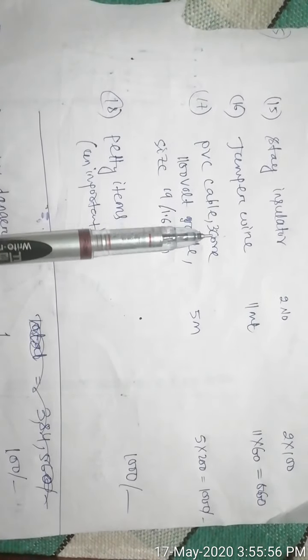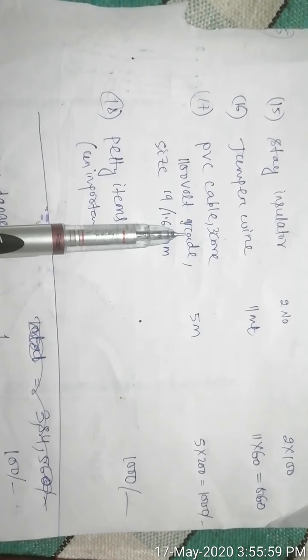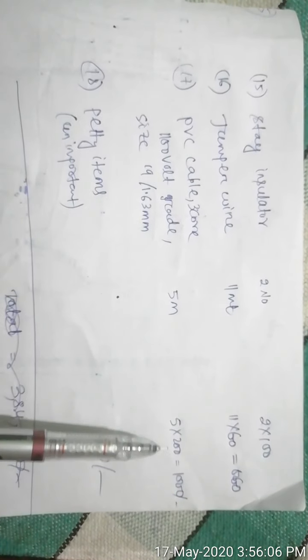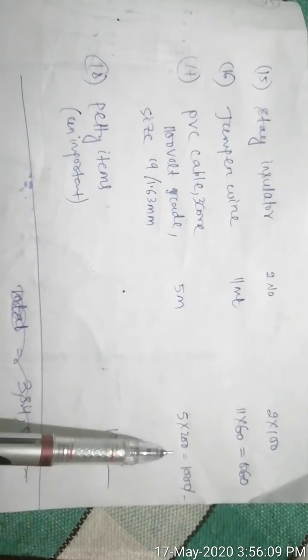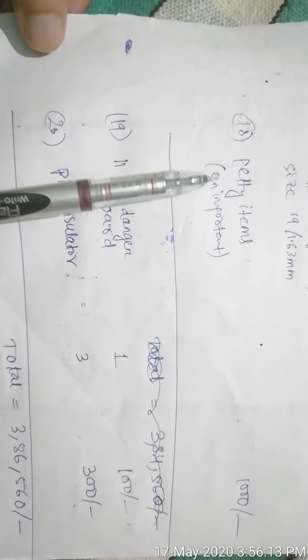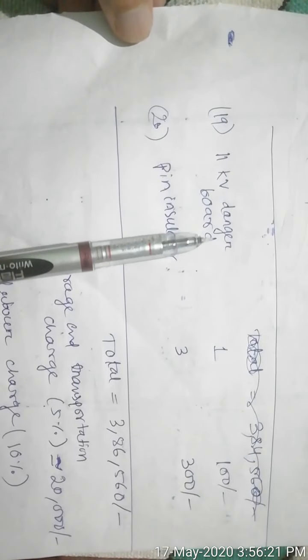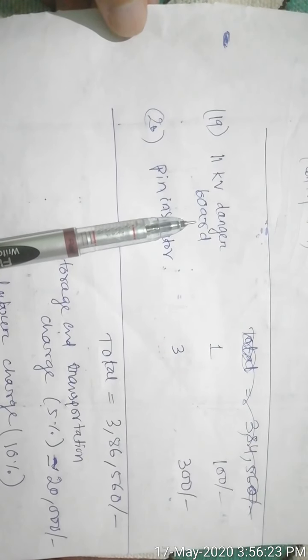Next is PVC cable, 3 core, 1100 volt grade, size 19 by 1.63 mm. 5 meters of it is required, and it will cost 1,000 rupees, because 1 meter costs 200 rupees. Next we will include some petty items. These are some unimportant items. We will cost it at 1,000 rupees. An 11 kV danger board is also required, which will be put on one of the pole structures at a height of at least 1.5 meters from the ground level. It will cost 100 rupees.